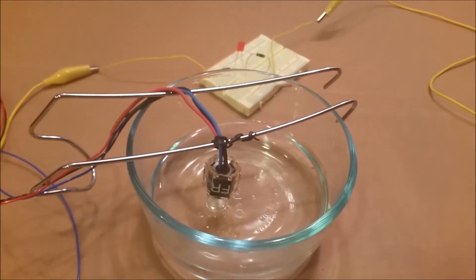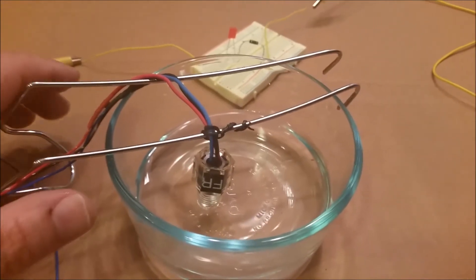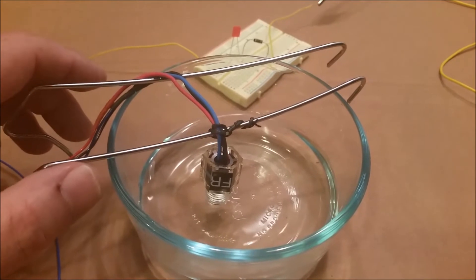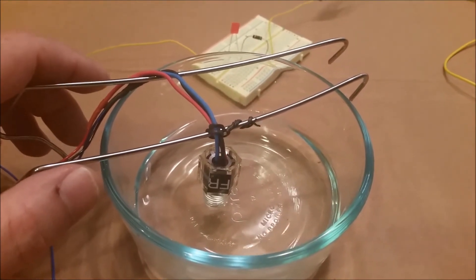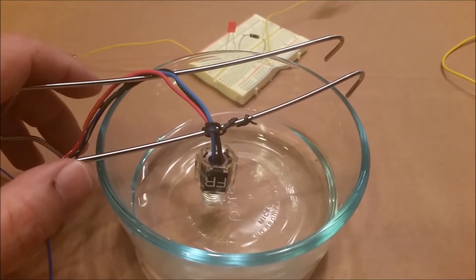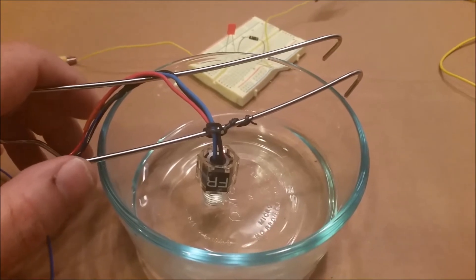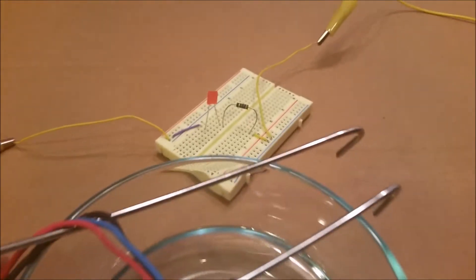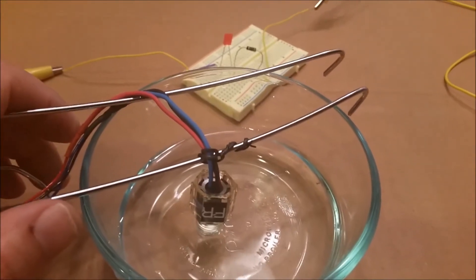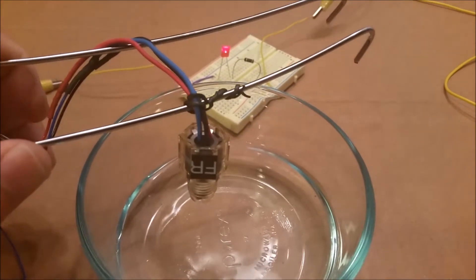So you'll see if in the sump the fuel was to go low below the sensor, then that light should turn on. So let's test it out, and there you see it working.